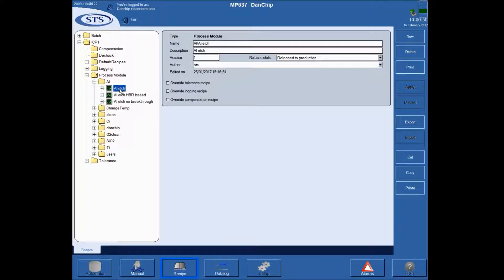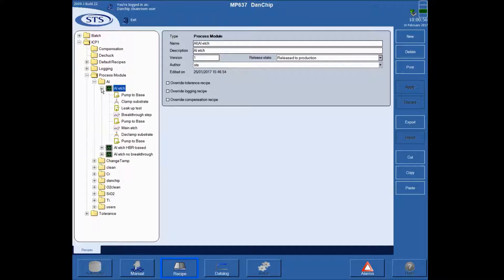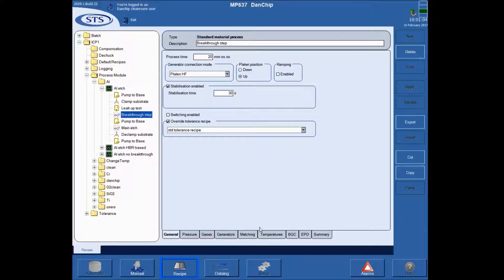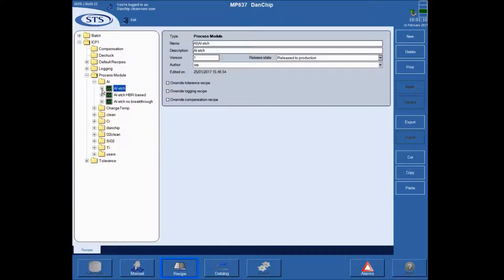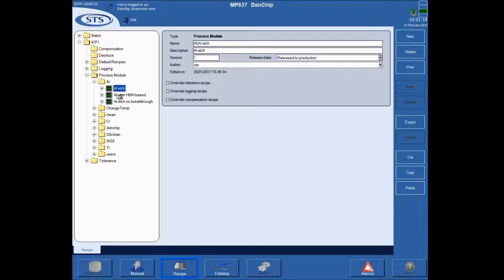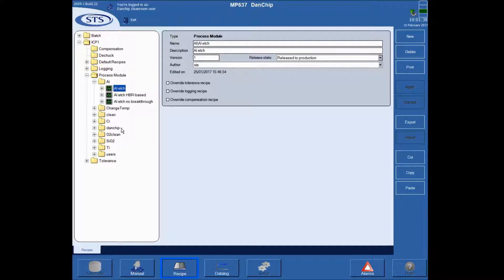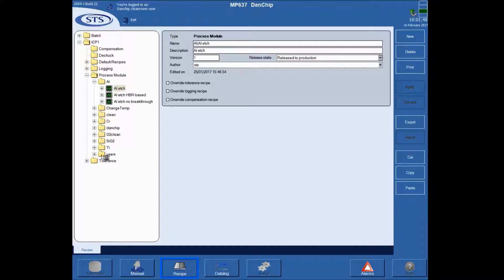Say I want to use this recipe for a certain time. It hasn't been created yet. It's pretty obvious that looking through all these steps, what you care about is typically the process step. All the other ones are more or less invisible. So, the bottom line is you don't create an etch recipe from scratch. You copy an existing one and then put it in your own folder and change it there. You don't create it from scratch because there's a lot of hidden parameters in it. The only way to create and modify recipes is to... There's no save or close or save as. The only way to do it, or drag or drop for that matter, the only way to do it is to go to copy and then locate your folder.